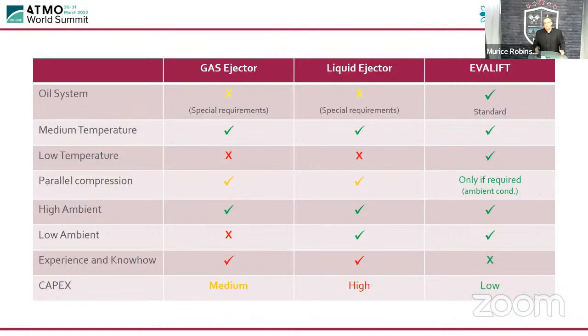Experience and know-how is quite important. A gas and a liquid ejector is a little bit complex for certain mechanics, but EVALIFT is very, very simple and straightforward. You can open the book up and it can explain to you exactly how it works. And then also with regards to CapEx. If I compare the three, gas ejectors on a medium, liquid ejector is high because there's a lot more equipment that you need to put in to use that type of ejector. But with EVALIFT, like I said, it's very simple. It's 1 or 2 plate heat exchangers, a 3-way valve, and then the control system, which you put in anyway.